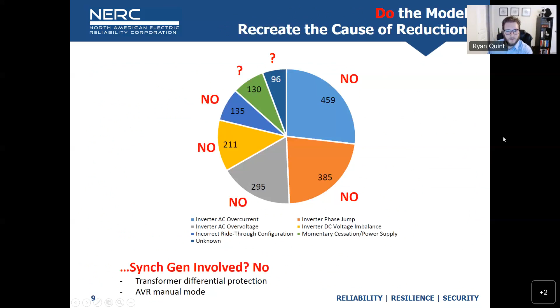Let me go back to the slides, the table. This is a good one. In the 2021 event, this was the number one cause of reduction, PLL loss of synchronism, from one manufacturer. We worked pretty closely with that OEM during the event and recognized that protection could be disabled. We asked, what is that protecting? And after really detailed analysis by the OEM, the answer was that it's not protecting anything. There are other forms of protection that keep the inverter safe, but that one was preempting all the tripping. So it seemed you've got an unnecessary protection causing spurious tripping in your inverter, so let's go ahead and disable it.